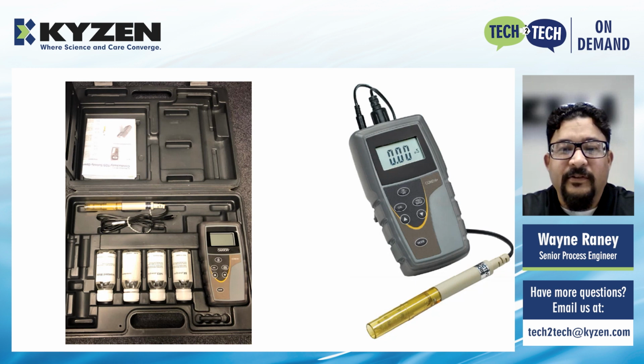Another thing we did was show the customer how to perform a side-by-side check with a handheld conductivity meter to compare it to the automatic CCS reading. It's recommended to perform a calibration check using the same fluid for the CCS and for the handheld meter.